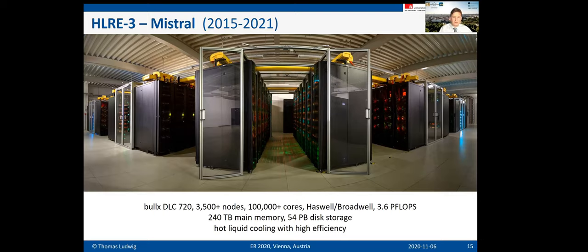This is a picture of our current machine: about 80 racks with hot liquid cooling, which is highly efficient. We use approximately 1.4 megawatts of electrical energy, costing 2 million euros per year in electricity alone. The unit for calculation is flops — floating-point operations per second — and this machine has 3.6 petaflops, that is 3.6 × 10¹⁵ floating-point operations per second.